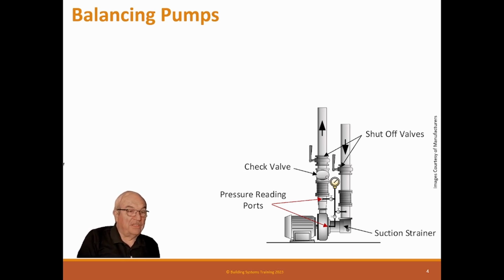And here's the second reason not to ever specify or try to put in a triple duty valve. There are different kinds of triple duty valves. There are a certain group of them that have stainless steel shafts that come out in a rotating device, and you screw them in or screw them out to adjust that valve flow meter inside the valve. There are other ones that just have a hand wheel and a gear rotation in there. Those are fine. They don't screw up. But I tell you, the ones that have the stainless steel shaft you screw in and out, in a couple of years you can't move it. Somehow the rust fines get inside that packing, and they become impossible to open and close.